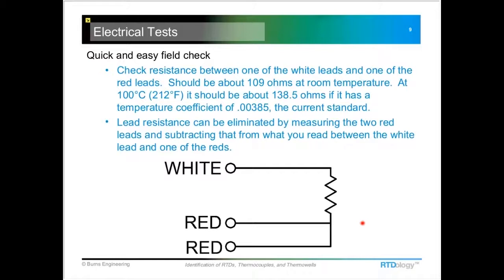And if we want to get a little more in-depth, we can go ahead and compensate manually for that lead resistance. We just take just a simple ohm meter, check between the two red leads and measure that resistance, and then subtract that from what you measure between the white and just one of the reds. And that will give you the resistance of just this sensing element right here. It's a little resistor made out of platinum wire, so that's what you're measuring and that's what you want to define.